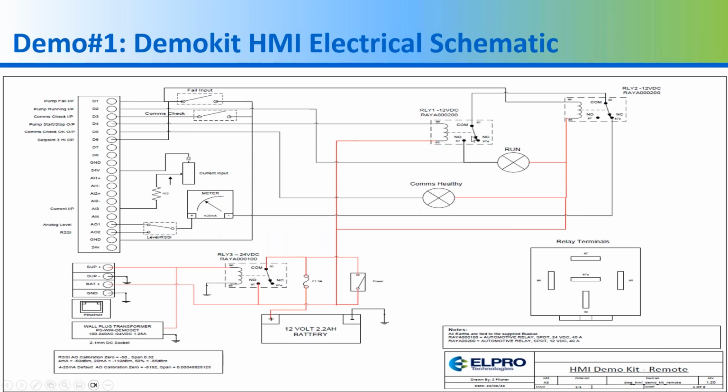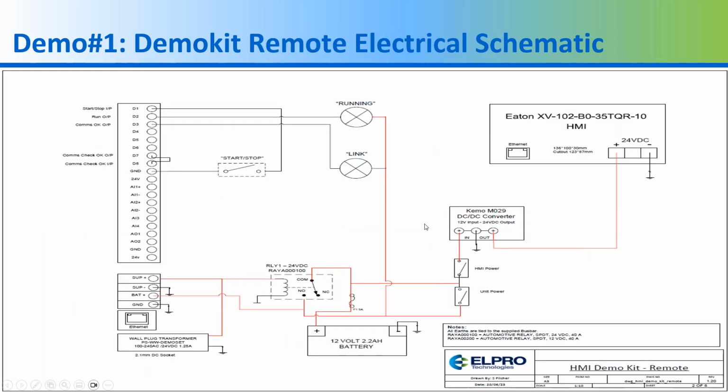Here's the electrical schematic where I am monitoring the start-stop. I'm monitoring the run light and the comms healthy. I'm also monitoring the supply voltage and battery voltage. And this is just a schematic of the remote.